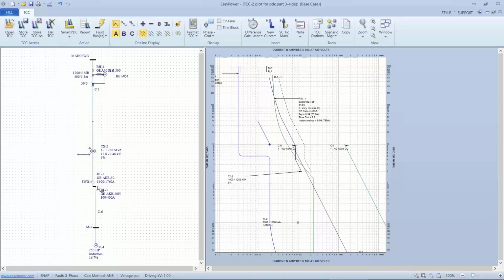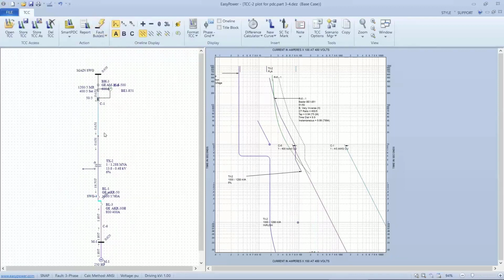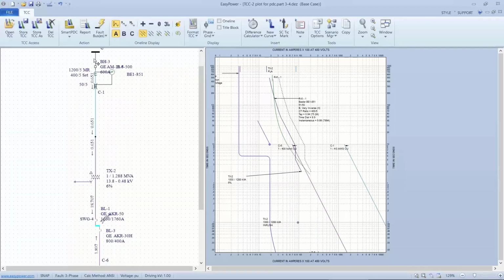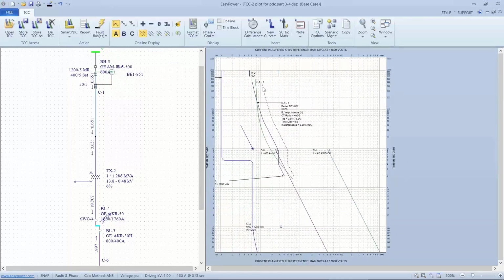My worst case current, if I fault this bus, is 651 amps. And if I make that in reference to the 13.8 range, here's my max fault current of 58.4 amps. Here's my transformer pickup set at 75 amps, which seems like a reasonable place to be. I'm not protecting it well enough on my frequent fault curve, so I probably want to come down a little bit on my knee. So that's a good first order approximation.